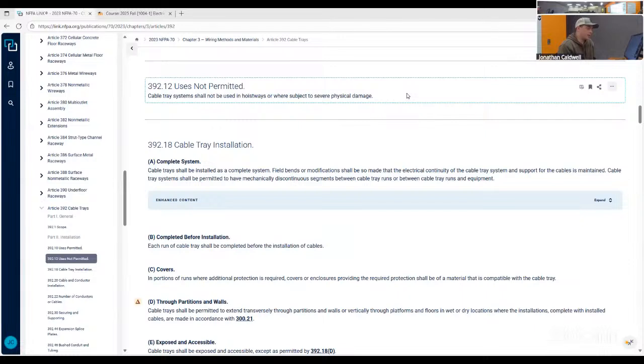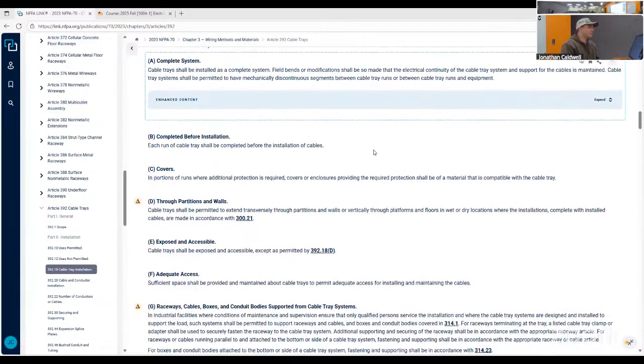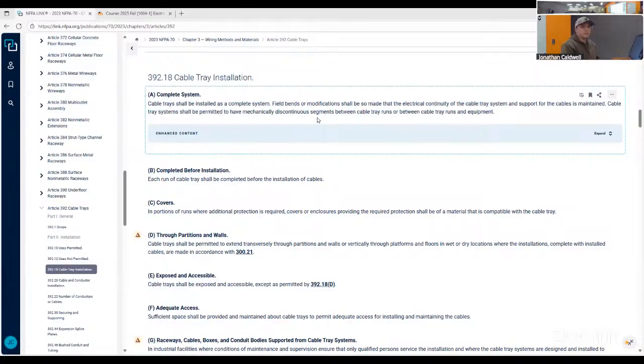We have installed tray in hoistways, but it is not above equipment that can be hoisted. Does that make sense? So there should be no possible way for that tray to get damaged. Even in this new building we're building, there's a pipe rack that we built right on top of, and it is in the hoistway. The pipe rack is in the hoistway as well. But there's no way that a piece of equipment will be hoisted above that tray. That's why it's allowed. The workers understand that. Cable trays have to be in a complete system, just like any other raceway.